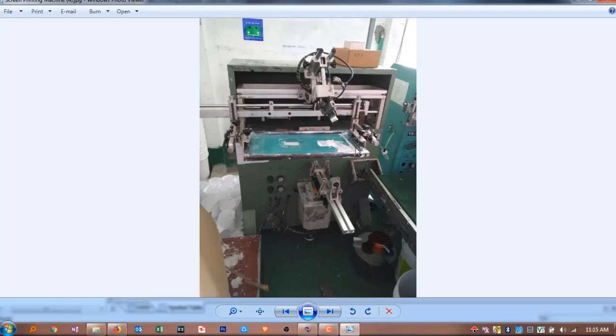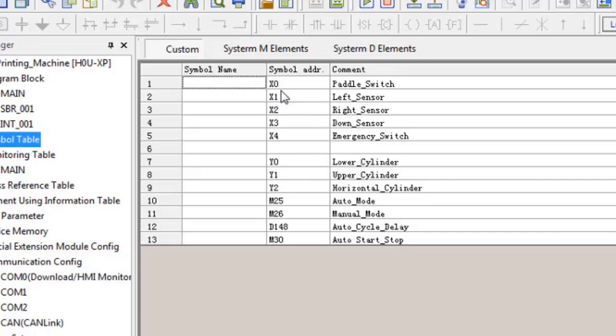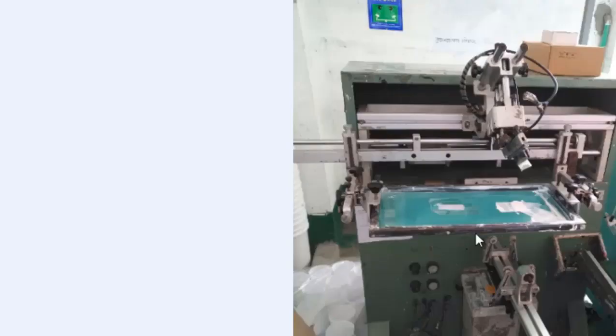There are three output cylinders and several inputs: the paddle switch, proximity sensors, and an emergency switch. We have mainly four inputs — three sensors and one paddle switch — plus one emergency switch. The inputs are: x0 = paddle switch, x1 = left sensor, x2 = right sensor, x3 = down sensor, x4 = emergency switch. Outputs: y0 = lower cylinder, y1 = upper cylinder, y2 = horizontal (left-to-right) cylinder.